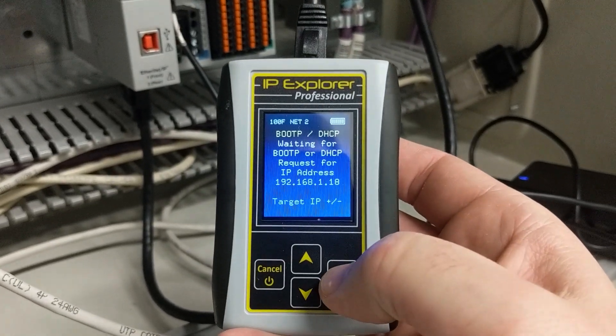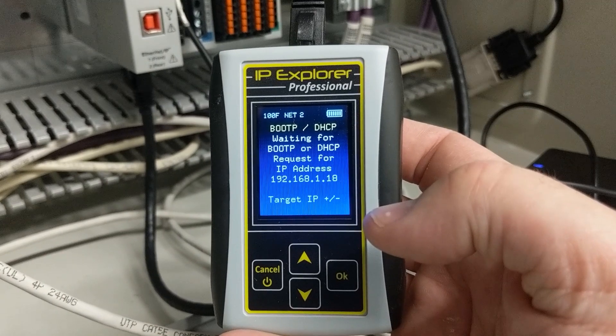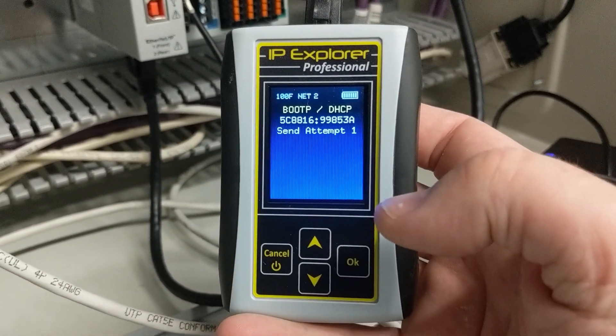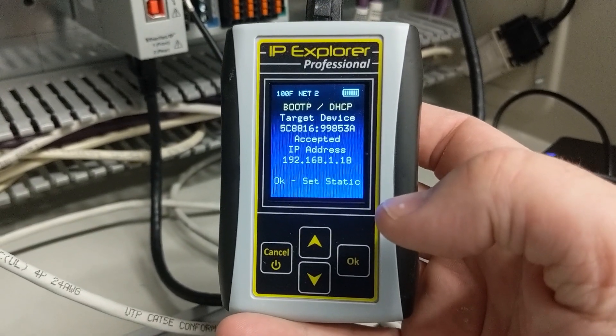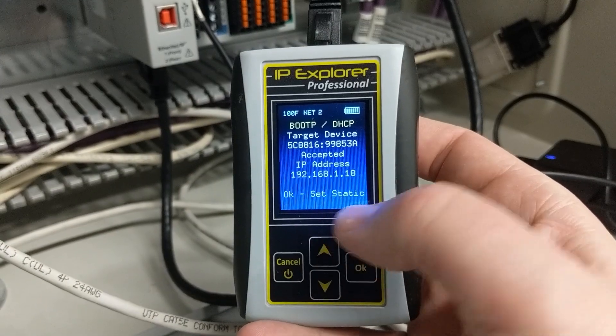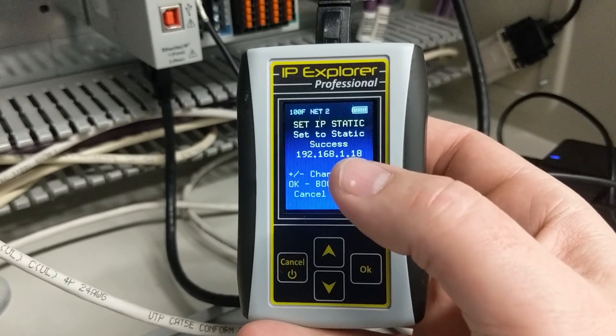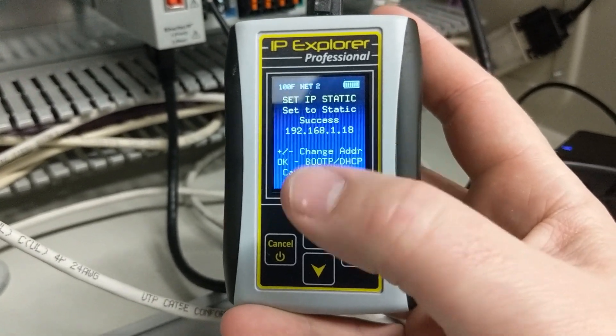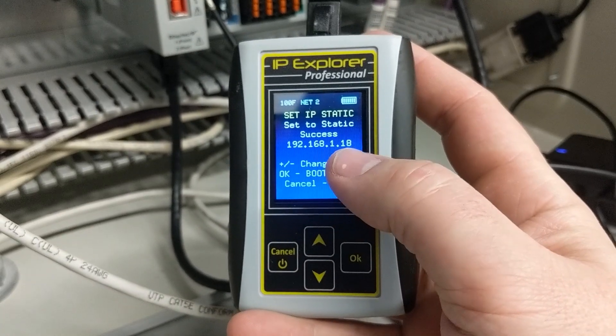So we're going to use BOOTP/DHCP, and we're going to wait on a request. We may have had this powered up too long — many devices will quit making BOOTP/DHCP requests after a certain amount of time. Okay, it did accept it. So if we want to set this to static, we're going to click the OK button. It successfully set it to static. This CompactLogix is no longer looking for BOOTP/DHCP. Next time you power it up, it will have the IP address 192.168.1.18.